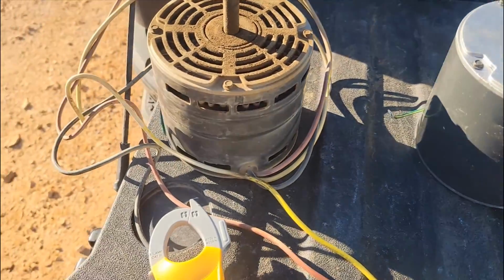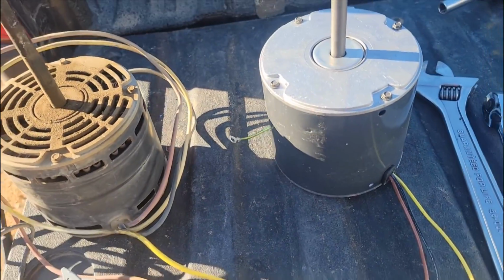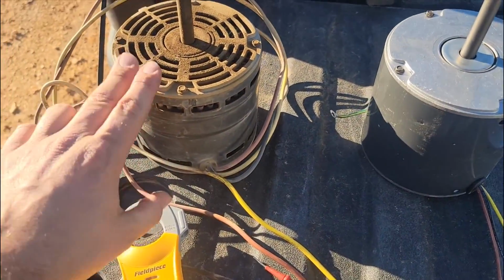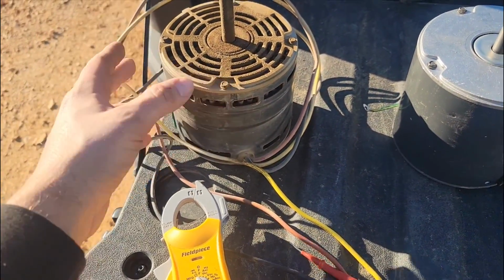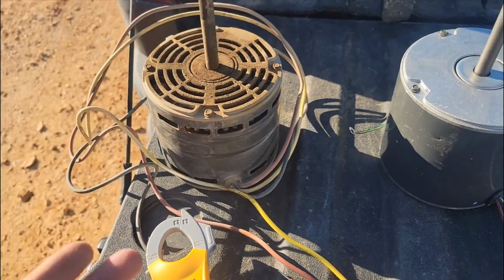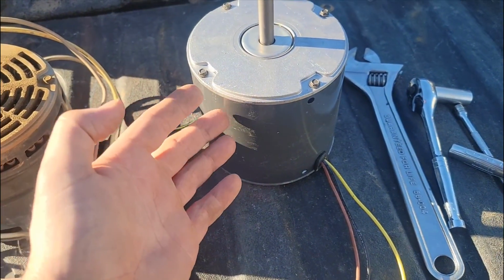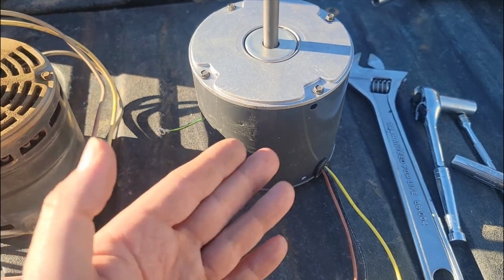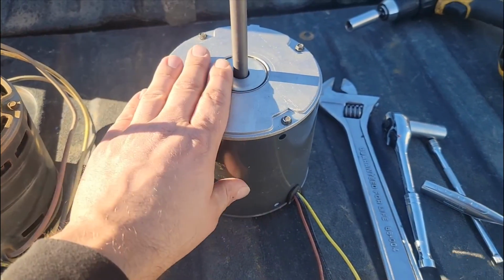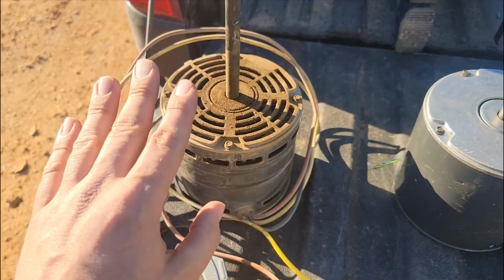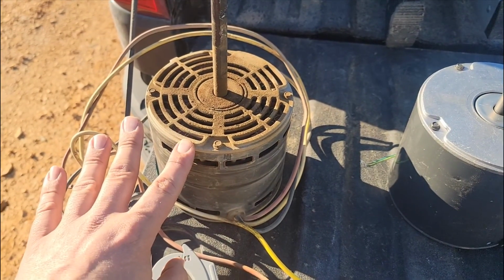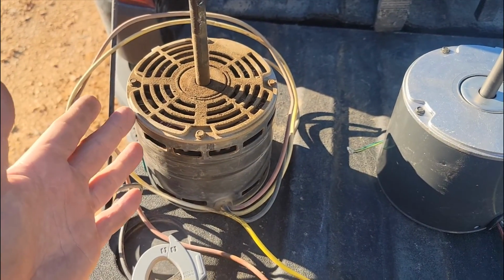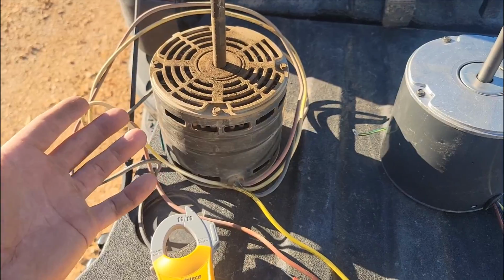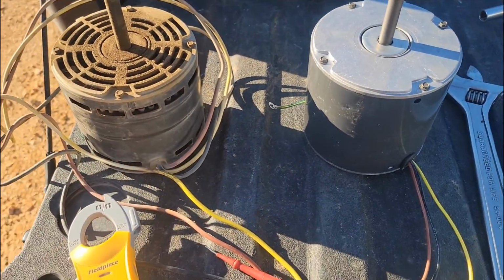You see any difference between these two motors? I do. I see a lot of difference. I see the fact that this is like an open type motor because of the fact that it's got all these vents to let air in here, but the new motor they sent me is closed type motor, which most condenser fan motors are supposed to be closed type motors, and most evaporator fan motors, or indoor motors, are open type. But this is very unusual.